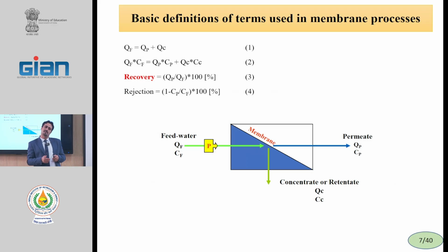Based on the process, we usually have 75% recovery. Sometimes we can increase it to 90% based on the feed concentration. If the solute concentration is low, we can increase the recovery ratio. Therefore, recovery shows how much product can be produced.